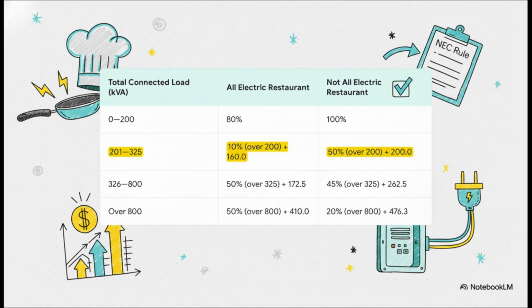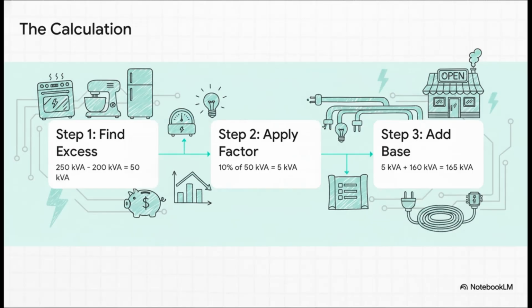Let's look at the first scenario. Smaller places, 0 to 200 kVA total connected load. How does it play out there? Okay, if it's all electric, the code gives you a nice discount right away. The calculated load is just 80% of the total connected, a 20% reduction. Recognizing not everything's on at once, but what about the not all electric in that same range? Gas stove, maybe? If you've got gas or other fuels for major appliances, it's different. Below 200 kVA, the calculated load is 100% of the total connected load. Wow, no discount at all, 100%. Why so conservative for the not all electric places?